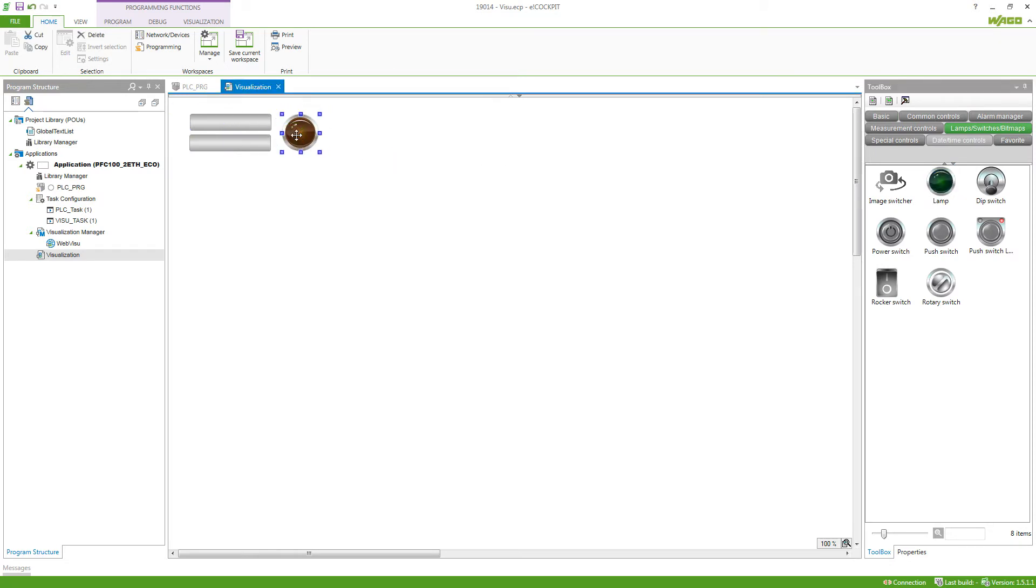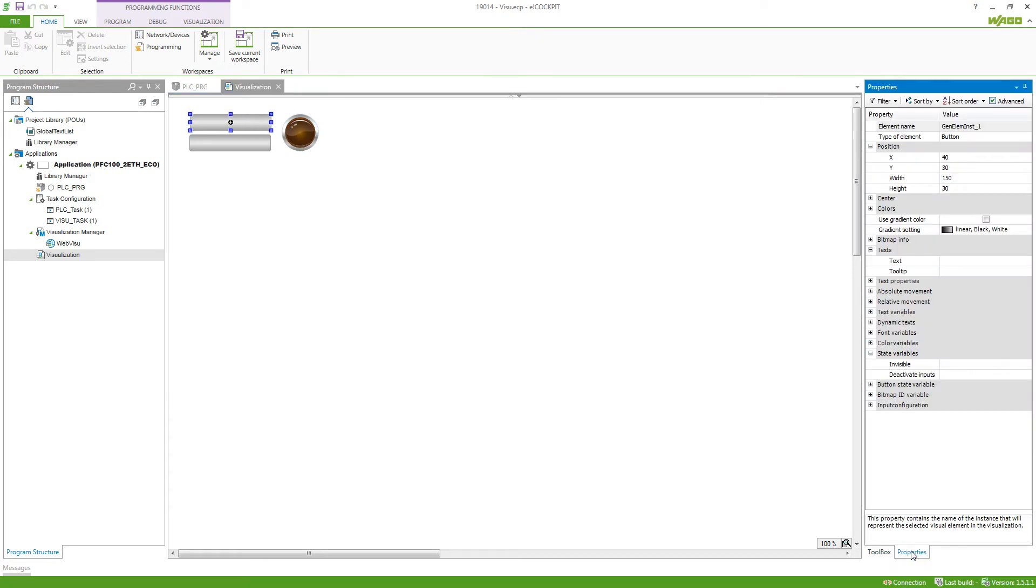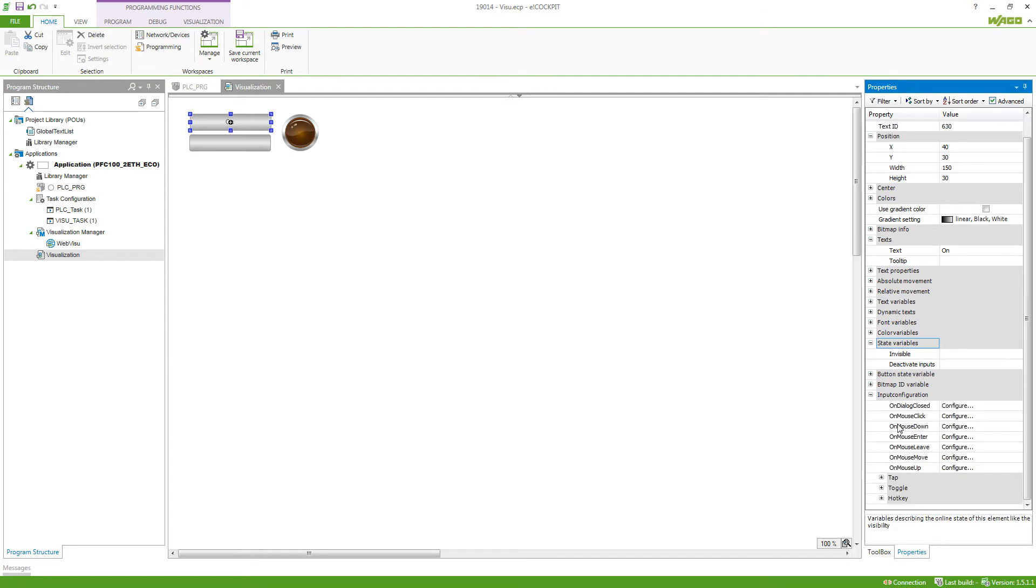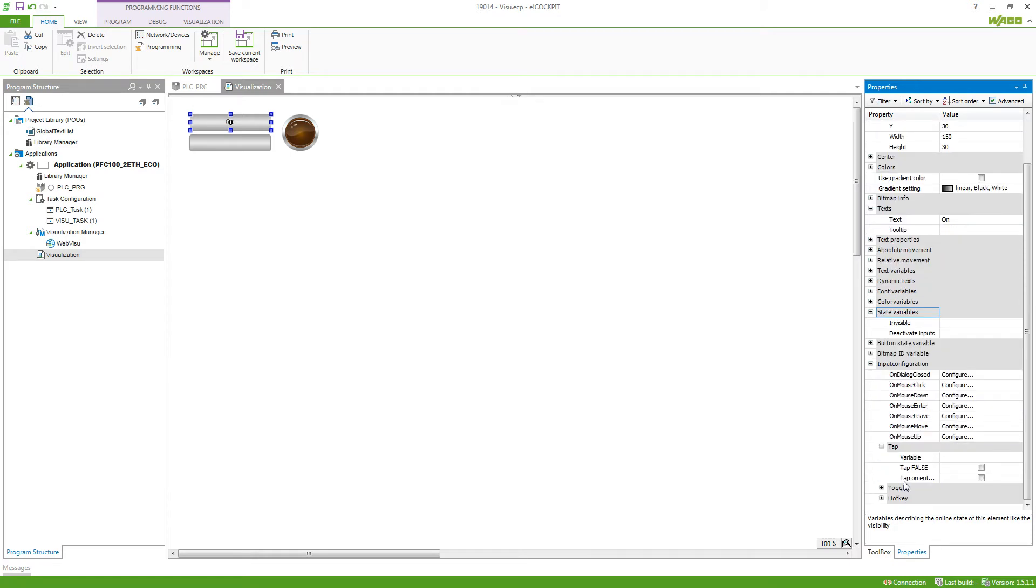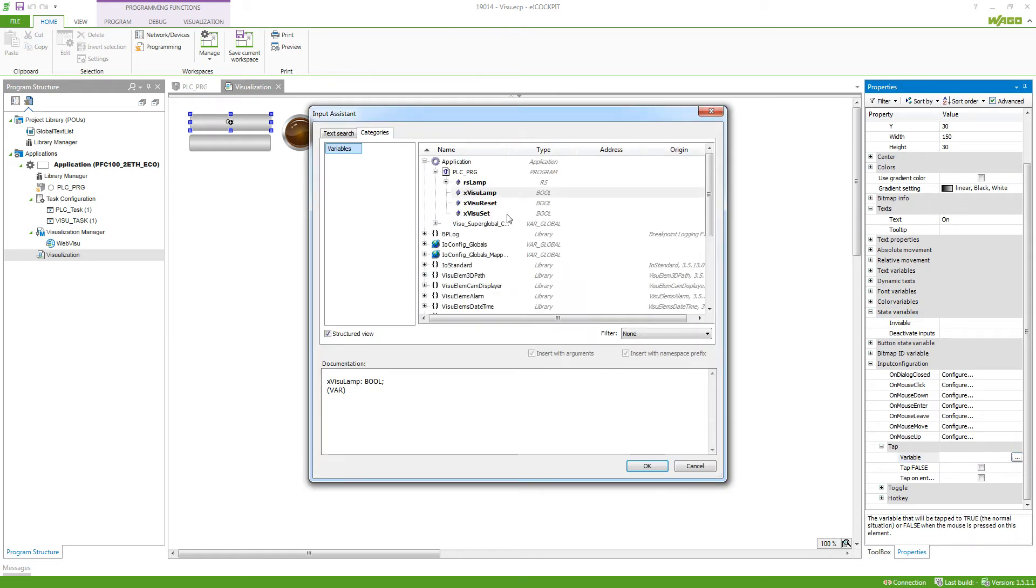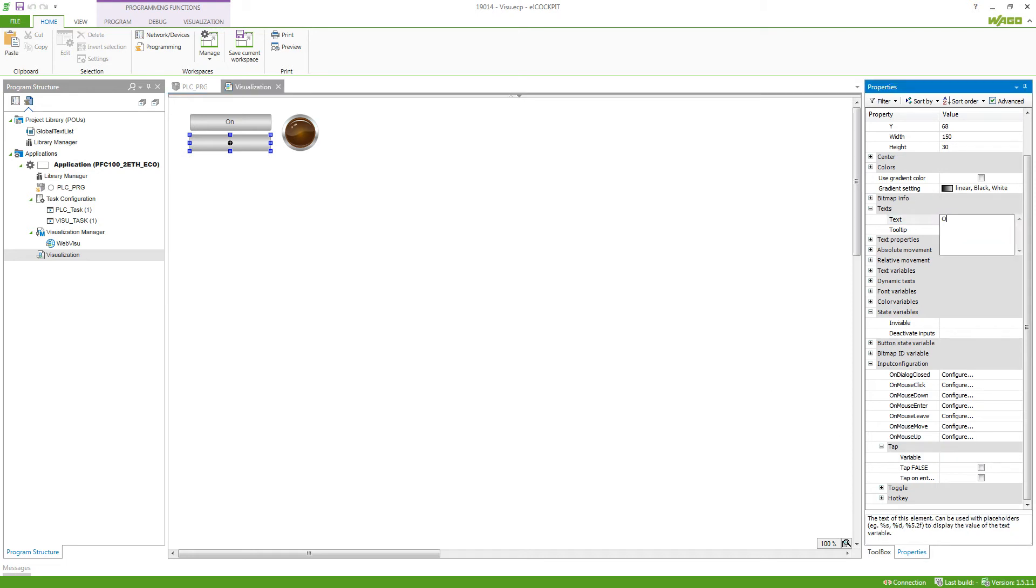So if we just align them we can now select a button and go to the properties. Here we can set a text, so for example on, and connect it to the variable. So we go to input configuration and then tap and select the variable here by using the three dots. Go into our application PLCPRG and then select xVisuSet. We do the same for the second button so this time we'll say off and again select the variable.